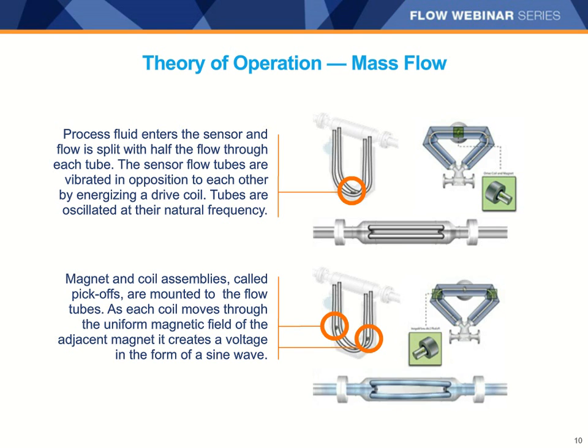With no flow, the meter tubes vibrate like you see here on top. In a Coriolis meter, the inertial force is provided by vibrating the flow tubes. Flow, moving through the tubes, tries to continue on its path perpendicular to the axis of vibration, resisting the movement. That resistance to the movement causes a deflection of the tubes in the form of tube twist. The tube twist, or angle of deflection from the vibration plane, is measured and converted into mass flow measurement.